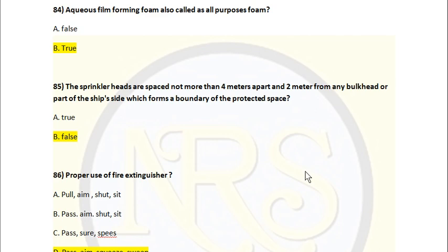It does not specify the distance or how far apart sprinklers should be; it only says each sprinkler has to cover 5 liters per meter square per minute. Accordingly, you place your sprinklers, and one branch of sprinklers cannot have more than 200 sprinkler heads. One branch of pipeline, whether on one horizontal surface or one vertical surface, should not have a common connection of more than 200 sprinklers. This is what the regulation says. So for question number 85, option B, false, is the correct answer.